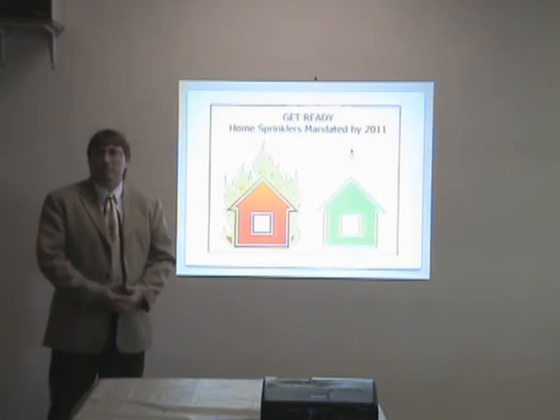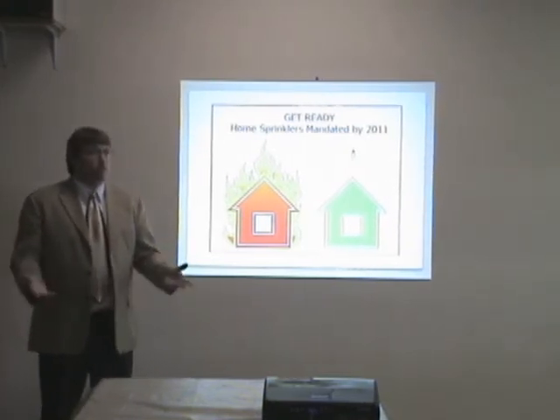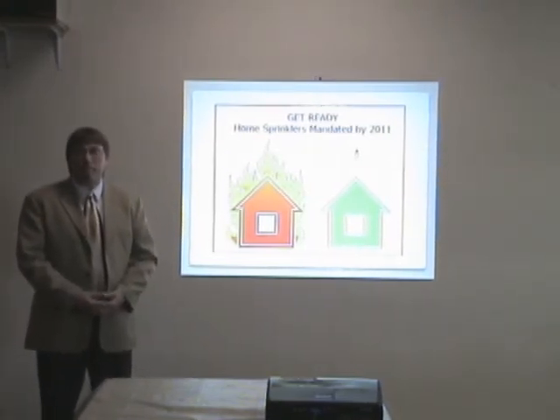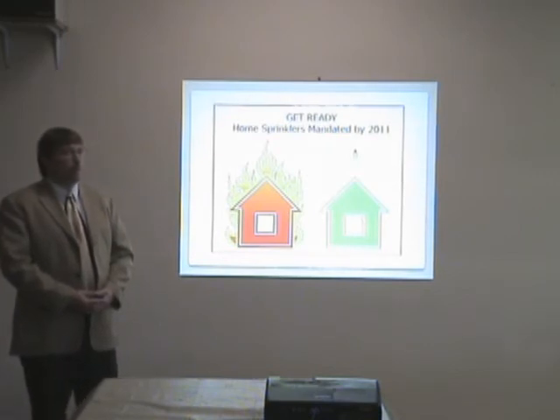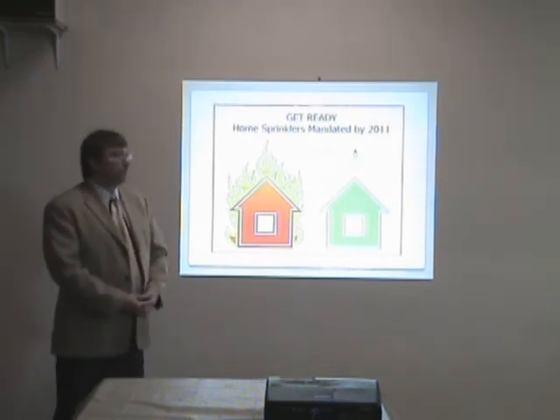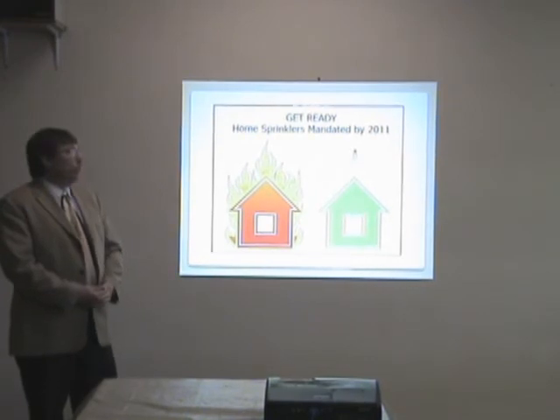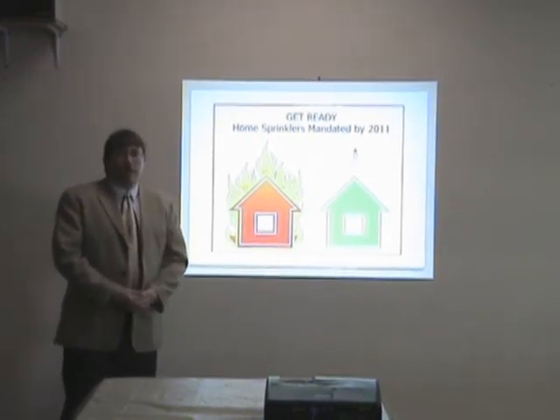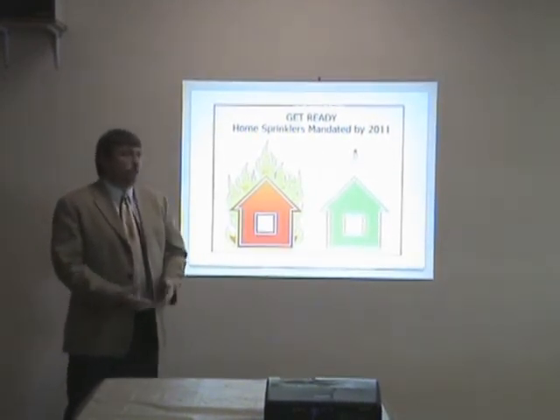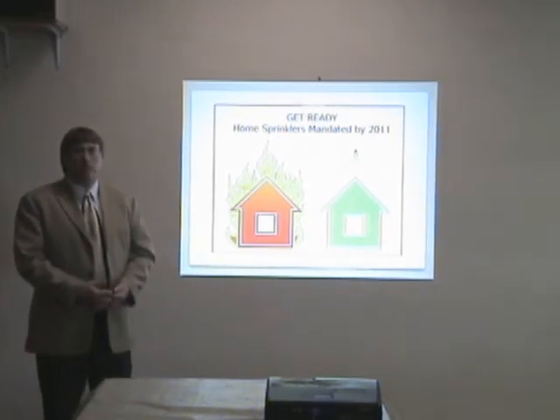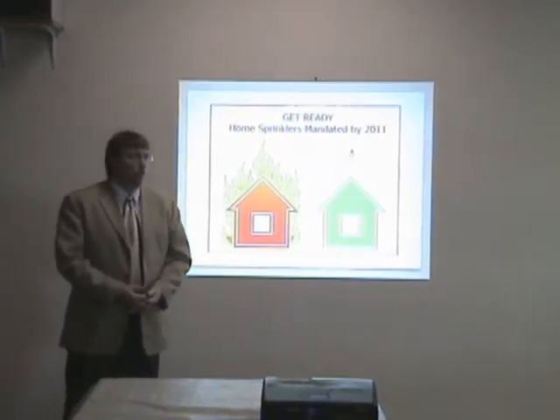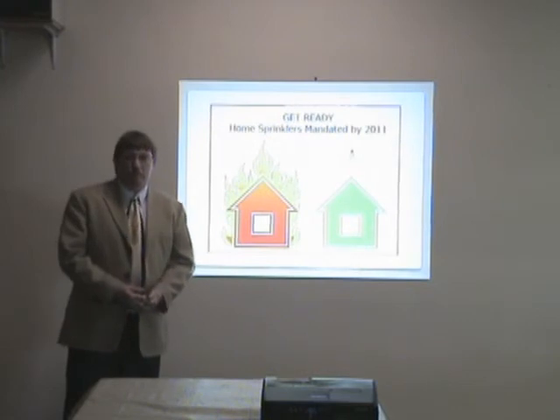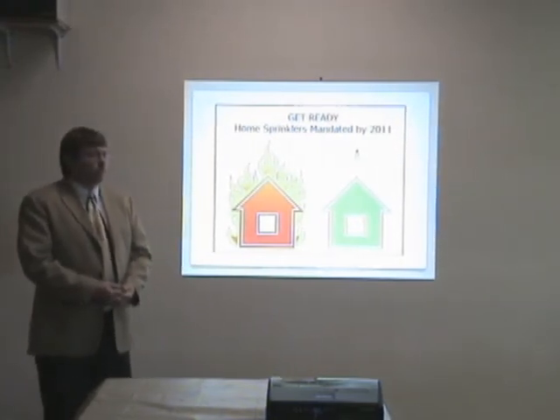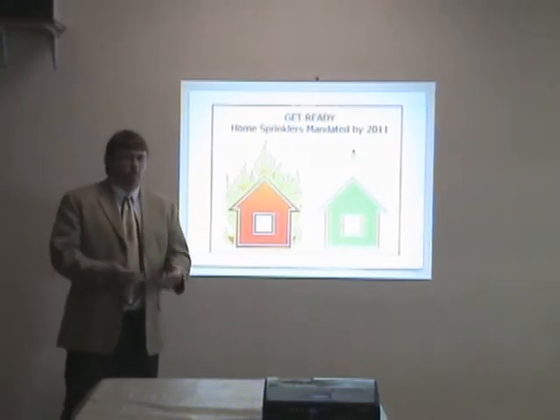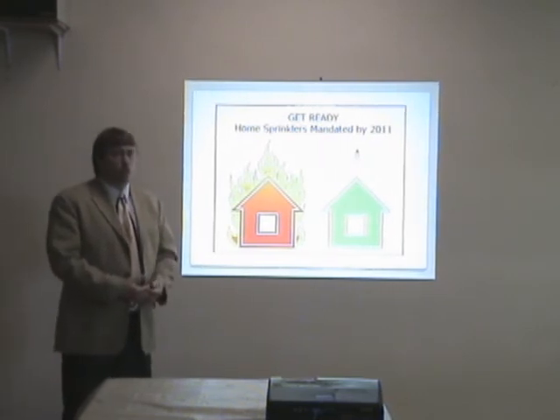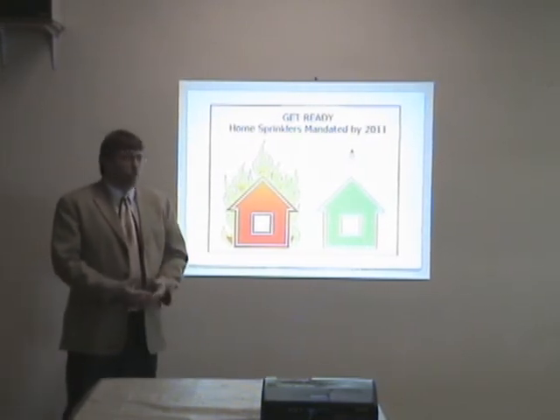Are there any questions about residential sprinkler systems or sprinkler systems in general? Where are you going to get all this water pressure when you're out in the country on a well? Well, we have systems that are designed in order to provide that pressure. We can provide fire pumps, underground storage tanks, above ground storage tanks, different types of water supplies that we're able to use to provide the water supply and the pressure.